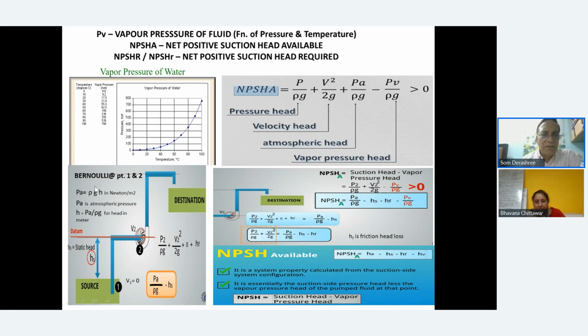Now, you are all aware of the simple energy balance equation, which is the Bernoulli equation. That is pressure head, velocity head, then static head, and whatever is the friction head. So basically what you do is you do a Bernoulli at this point, which is the source from where the water is coming, and at the pump suction. So if, let's say, it is point 2, then you will do a Bernoulli.